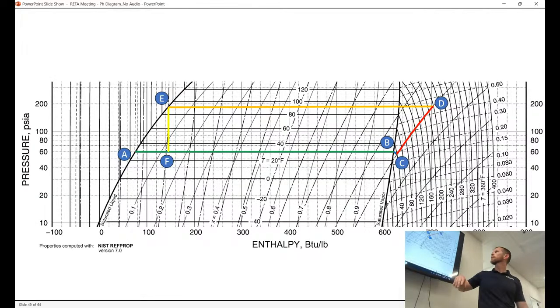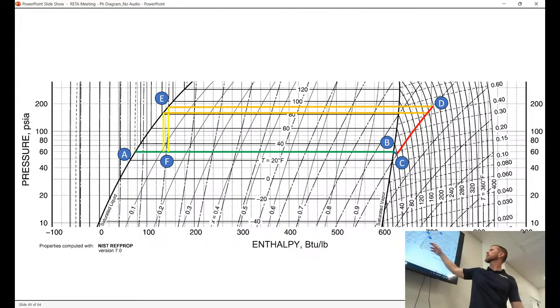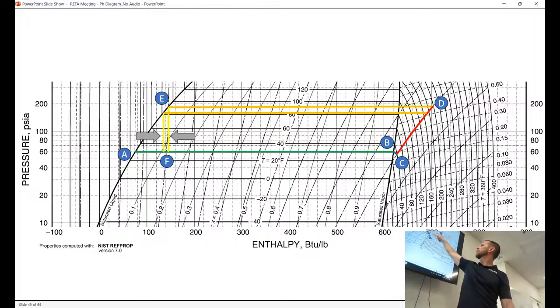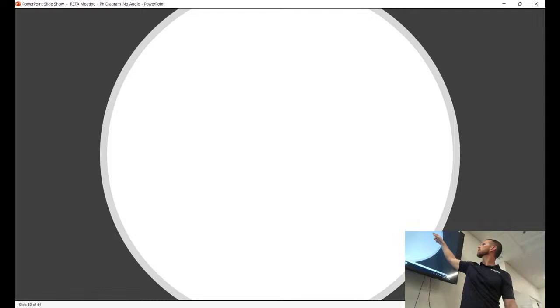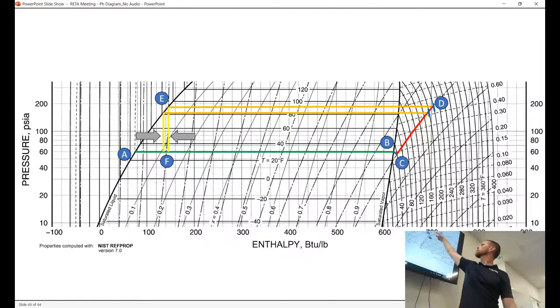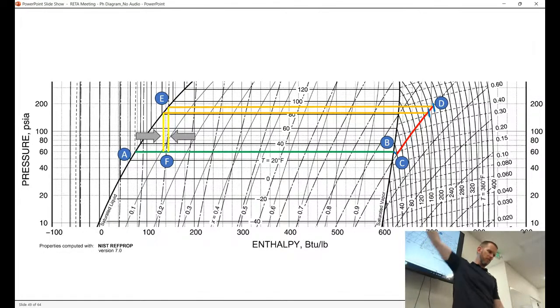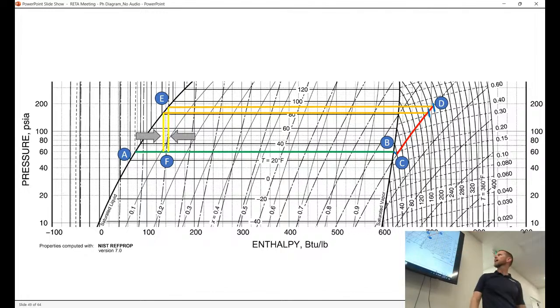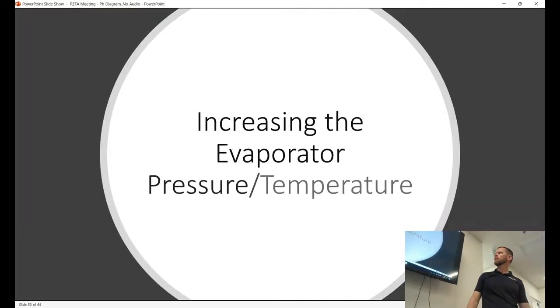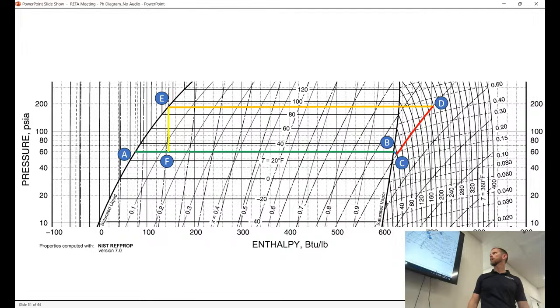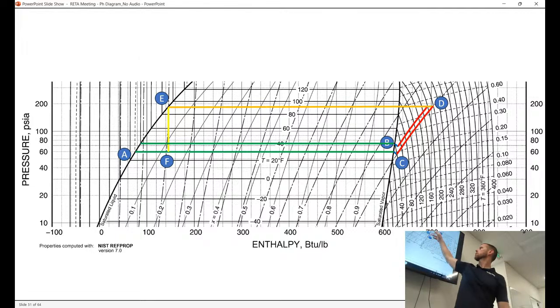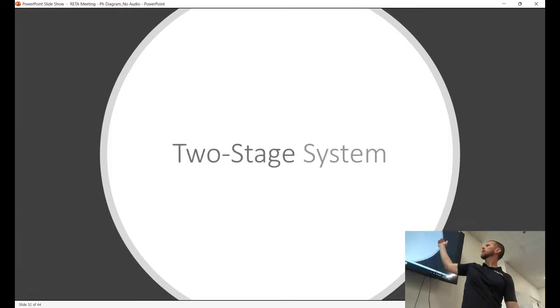Now decreasing the condenser pressure — that's the reverse of what I've already shown you. Our compression process ends at a lower temperature, and we hit the vapor dome further on the left, which means less flash gas. Then increasing evaporator pressure — you raise the evaporator pressure and you're going to have a lower discharge temperature and less flash gas. So increasing evaporator pressure is beneficial. Now the two-stage system — this obviously gets way more complicated.